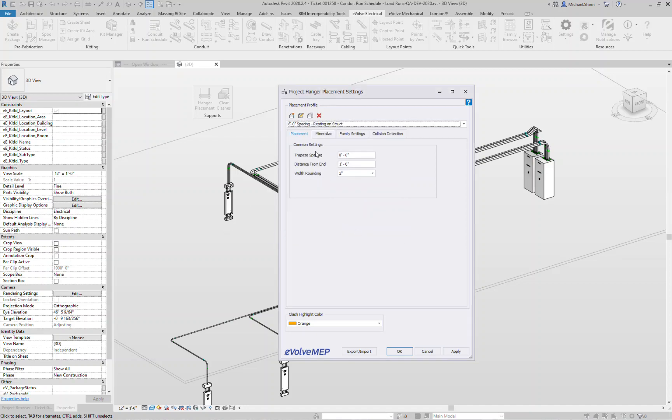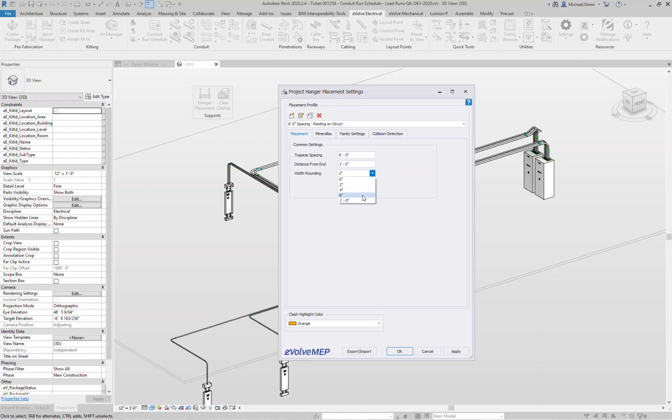So now I have the ability here to set what my trapeze spacing is going to be, maybe every six feet, distance from end, and then what's your overall rack width rounding, rounded to nearest two, four, six, or foot. If you put it to zero it's not going to do any overall rack width rounding.